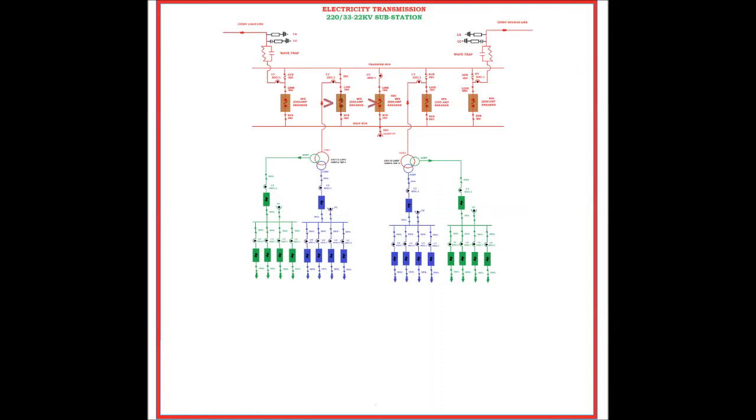In this condition, transformer one is being supplied through its own line and TBC as well. Now turn off the breaker of transformer one and open bus and line side isolators of the same. Hence we have isolated the breaker without interrupting power supply at all.